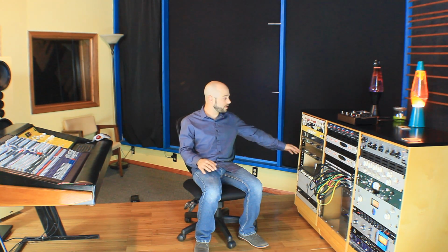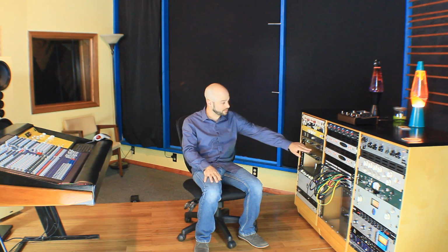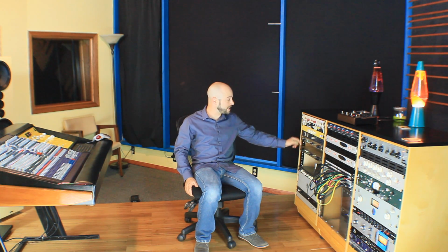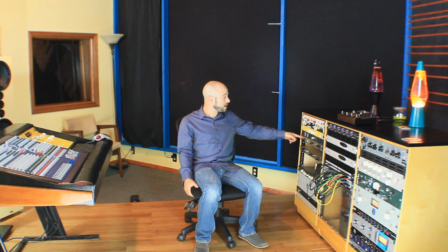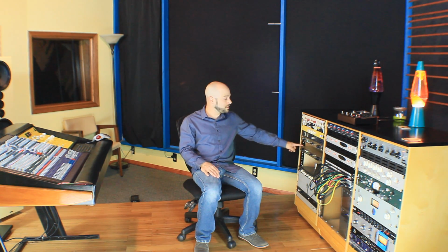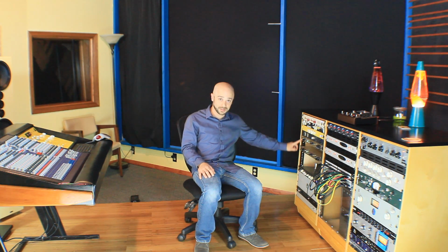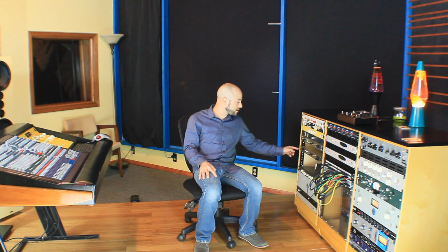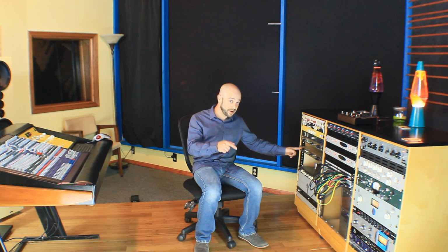You can easily encounter a ground loop with rack equipment because they all share a common rack rail, or two rails. And those rails, metal, you're using metal screws, the cases are all metal, so you're creating an electrical path between all of the cases, all of the enclosures. Each piece of equipment has its own path to ground through its own power cable. So when you then connect them all together electrically with the rack rails, you're creating a path from this unit to ground through its power cable, but also through the rack rail into this unit, and then through that power cable, and then so on through all of the pieces.